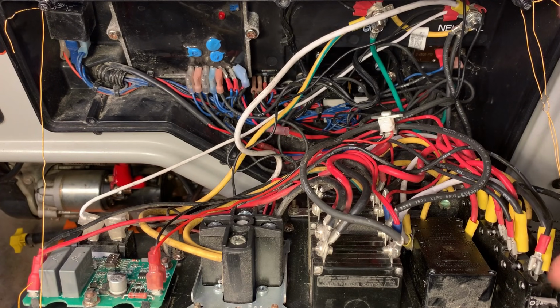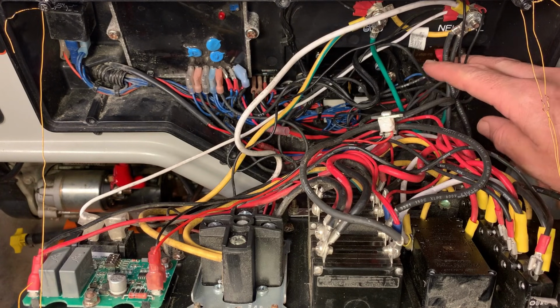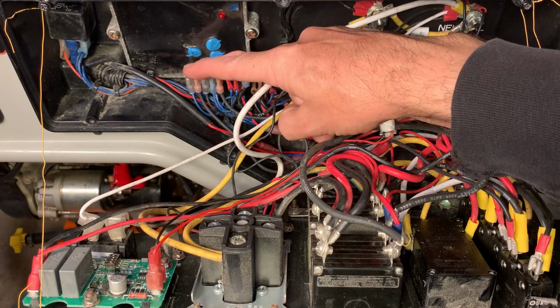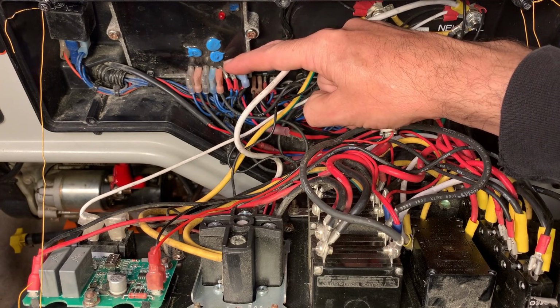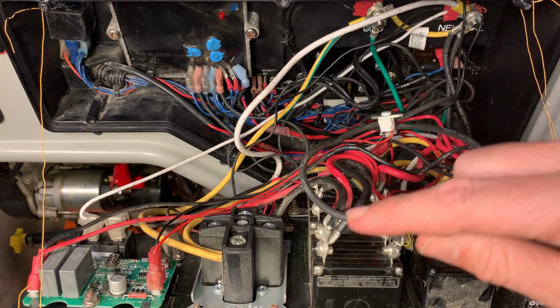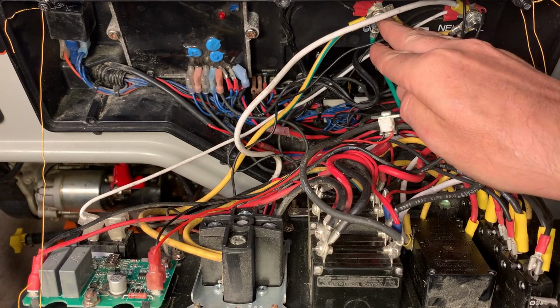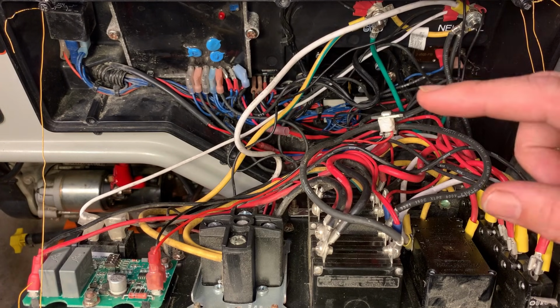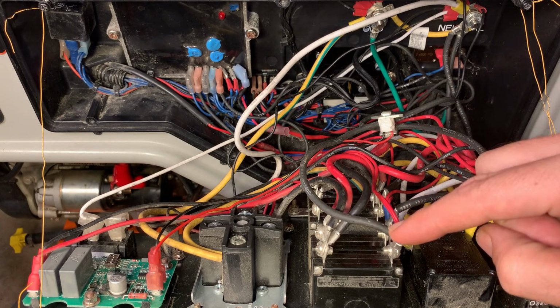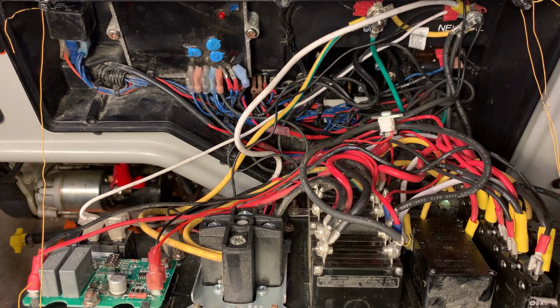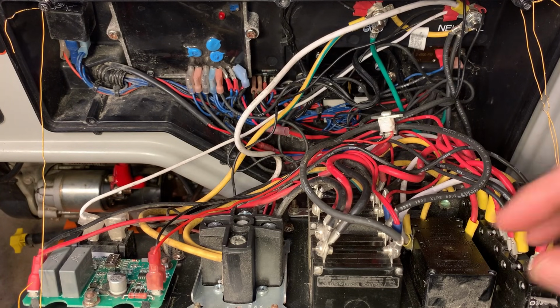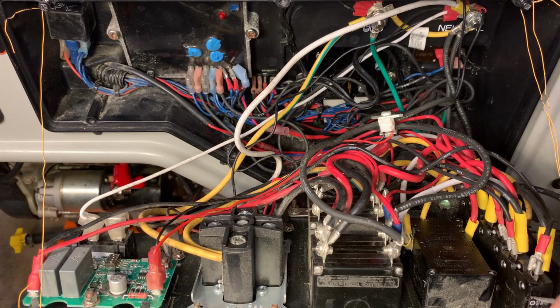But to do this test, you have to isolate the coils. That means removing the hot wires, removing the neutral wires for leg 1 and leg 2, disconnecting the DPE and isolating it, and disconnecting the sense winding and isolating it. Once that's done, we'll check each of those four coils to ground, and if that's good, we'll check each coil against the others to see if there's anything cross-connected due to an insulation failure. So I'm going to get these wires disconnected and resume with those tests.